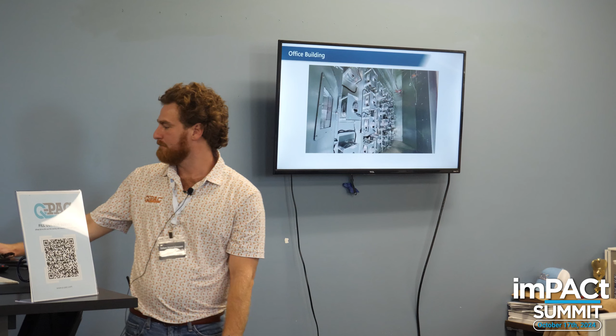And then factory installs as well — this presentation has mostly been about fan replacements and how you want to work on those, but we also offer Q-PAC that can go into almost all, if not most, factory or actual air handlers. So if you have a brand new air handler you want to put us into, there are situations where you can use a selection tool to get the air handler sized appropriately, and instead of using whatever fan comes with that selection tool, reach out to us and we can size one up for you to field install potentially.